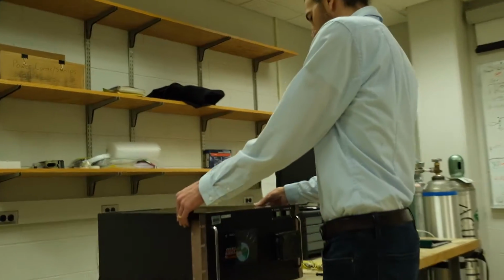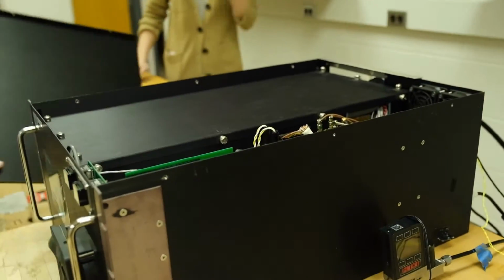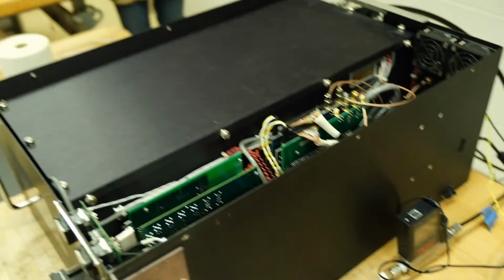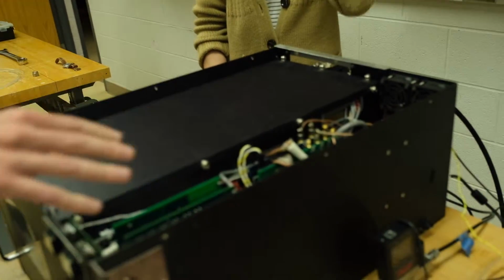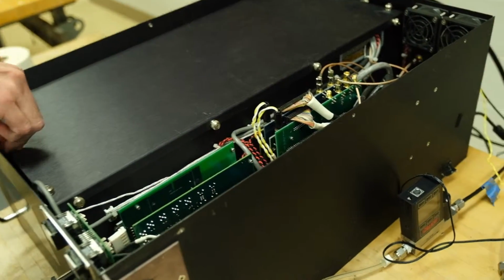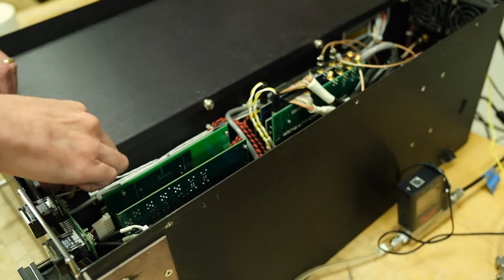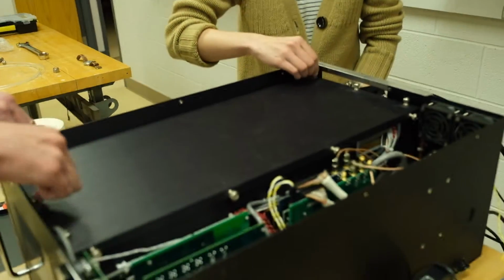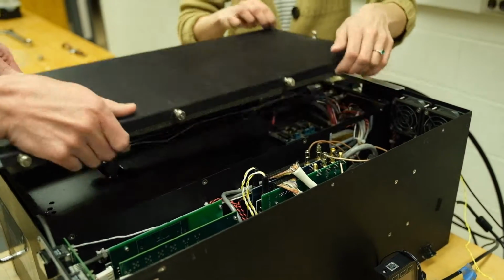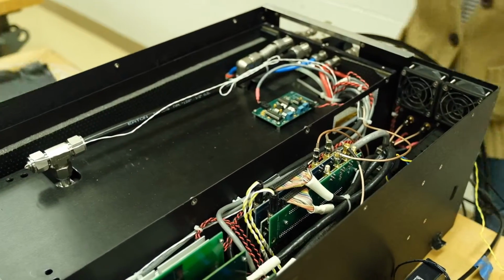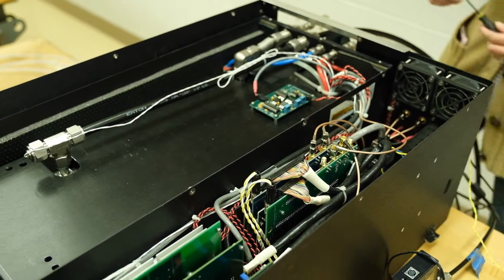So we can look on the inside of this one, if you're interested. This is the inside of the instrument. This part is all the computer type stuff. There's a computer, and also all the electronic controls and the power supply. This box that we're opening is the optical box, and it contains all the laser and optics and the cell where the actual measurements are made. Do you want to take off the other one too? We might as well.